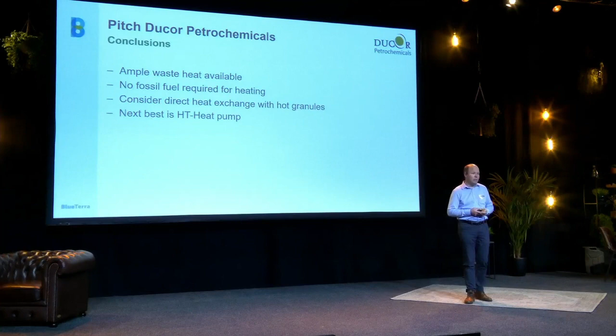Conclusions from this pitch: there's ample waste heat available at this site, and I think that's not only at this site, but a lot of sites do have waste heat available, usually at a lower level, because it's from cooling water. We can use it and really get the heat supply to the two heaters without any fossil fuel, so based on either direct heat or electricity. First of all, you consider the direct heat with the granules, and next best I would call the heat pump. So that's our solution to the pitch, and I think it's a twofold solution.